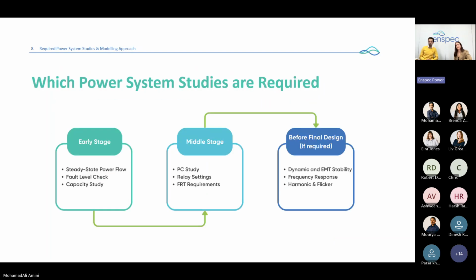At the earliest stage of the study, feasibility study, grid integration studies, and steady state power flow will be needed. Fault level check and capacity study could be done at the very earliest stage. After that, at the middle stage, protection coordination study, relay settings, and fault ride-through requirements are essential. Before the final design, if required, dynamic and EMT stability studies, frequency response studies, and harmonic and flicker studies from a power quality point of view could be done.